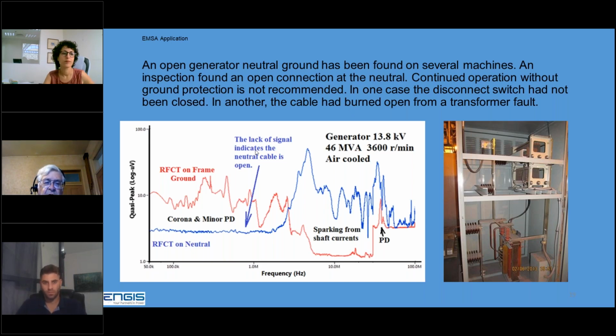The blue curve is the first connection. We put the RFCT around the conduit going up to the generator. Flat line at the noise floor of the receiving equipment. No signal. That cable is not connected to anything. It does act like an antenna from here up.